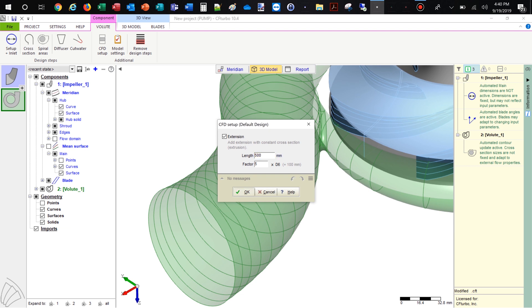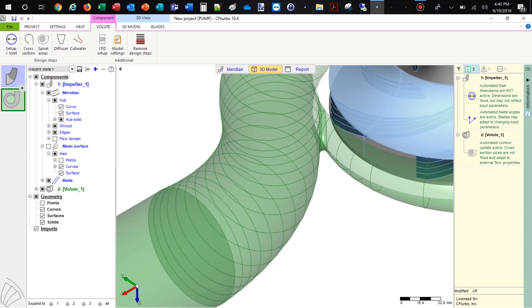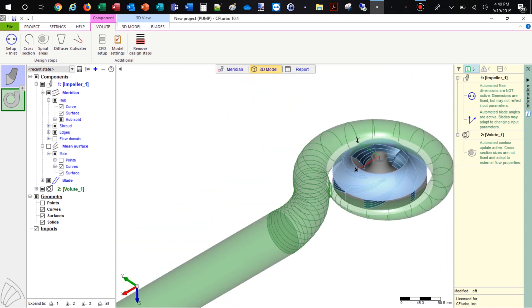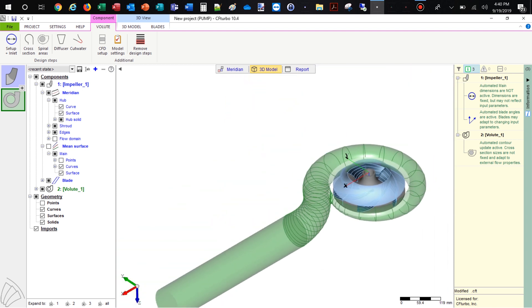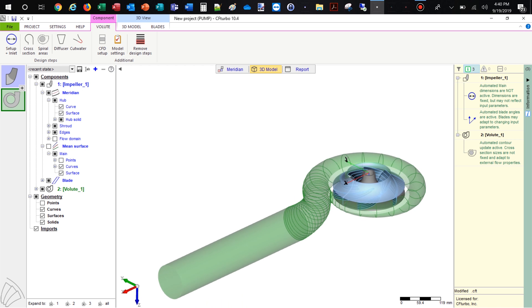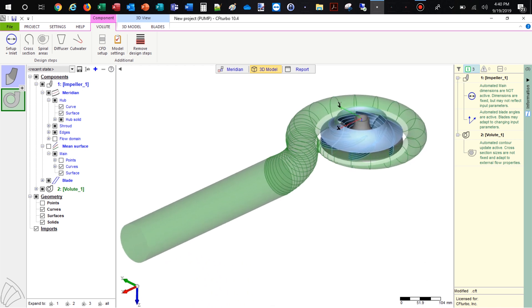To prepare the CFD model, we add an outlet extension downstream of the discharge diffuser. The pipe should have an appropriate length in order to prevent an impact from the boundary conditions to the pump stage itself.